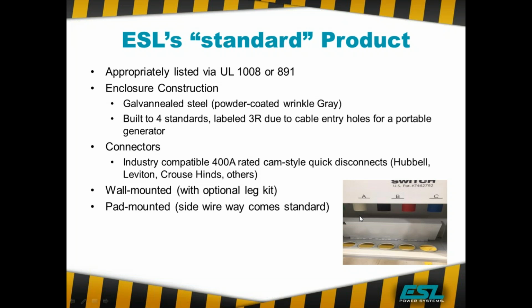Cams are Series 16, 400 amp, 600 volt rated cams. Number of manufacturers there you can see that provide those. They are all interchangeable. But keep in mind that there's still people out there that talk about connecting with lugs. And if somebody is going to do that, it takes a certified electrician. They're not always available in an emergency. Also, it takes much longer to do, which means you're going to be without power longer. So if they are afraid that their cables are going to show up without the proper receptacles, not a problem. We can sell them a receptacle kit and they can put together the connections fairly quickly. The units will come either wall mounted or pad mounted.